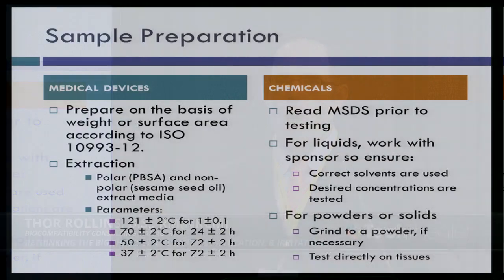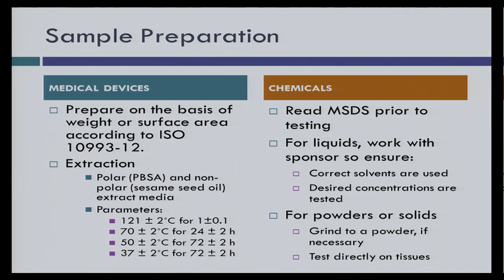In Europe, this in vitro irritation test is already accepted for chemicals, cosmetics, and medical devices. The FDA is not yet accepting it — they're waiting for more robust comparison data between animal and in vitro tests. Through a round robin study at the ISO 10993 level involving 13 labs worldwide, we are generating that comparison data. We believe the in vitro irritation test is actually more sensitive than the animal test, and could be used as a primary screen, with animal testing used only to confirm positive results.